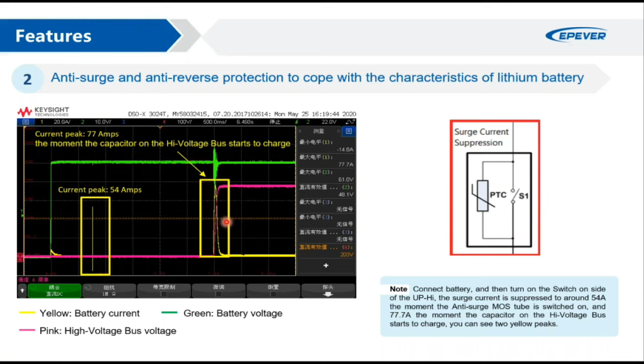And once the PTC is passed, now the capacitors on the high voltage DC side require a high amount of current. So the capacitors on the high voltage bus will start to charge, and this also demands a peak current of about 77.7 amperes. This is for this specific experiment. So there is a lag between the two current-demanding processes. If you add them up, that's a huge number, right? But by providing this trick and this lag between those two currents, you can solve this demand for high current and let the lithium battery work with your system actually. So this was about the anti-surge battery function.